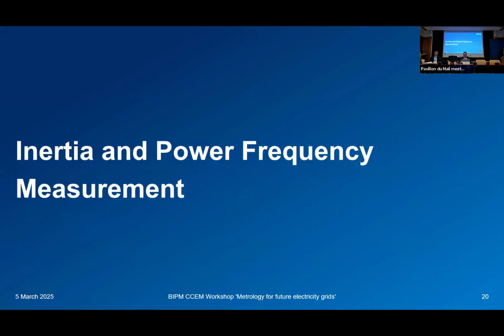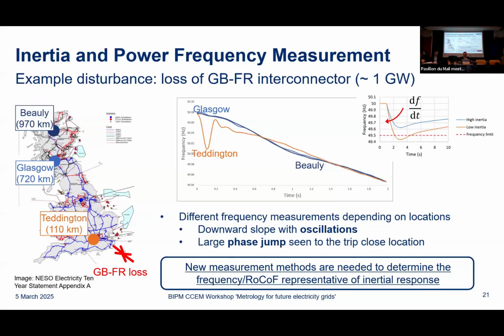And then the final topic that I'm going to touch on is inertia and power frequency measurement. So what's inertia? As I mentioned, it's this kinetic energy that's stored in the synchronous machines. And if you have a disturbance in the frequency, it's usually because there's an imbalance in the power supply of the electric power system. And those synchronous machines release this kinetic energy, and thereby they slow down the drop in frequency. So if you have a lot of synchronous machines, you've got high inertia, and then your rate of change of frequency is low.